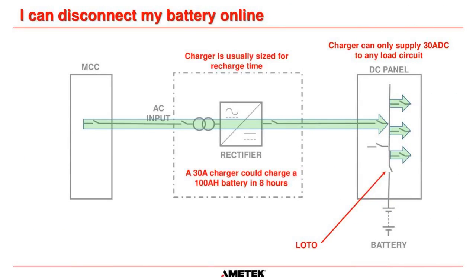The other reason why you can't do that is because of the design of a DC system. The charger is very, very rarely designed to carry the full load current of a system. Okay, the charger is usually sized for its recharge time. So basically, I'm saying here that a 30 amp charger could charge a 100 amp hour battery in about 8 hours. So the design engineer says, okay, I have a 100 ampere hour battery. So this battery here is 100 ampere hours. So I can connect a 30 amp charger to my 100 ampere hour battery, and I know my battery is going to be charged back up after a full discharge in 8 hours.